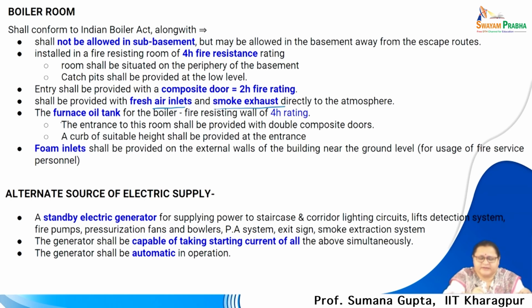Now, here the furnace oil tank is important, and that is why the high fire rating is required. So, doors even should have 2 hour fire rating. Foam inlets should be provided on the external wall of the building near the ground level for fire services. These are very important when there is a boiler room, and this 4 hour resistance is very high fire resisting material, usually concrete. It has to be enclosed within a concrete room with a 2 hour fire rated door.